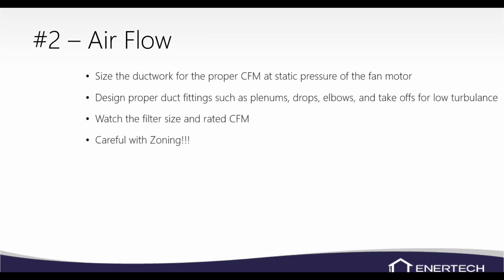Zoning, you can run into a problem with zoning. We do like to make sure that you have a bypass damper on your zoning. So if you have a small zone that's calling, we don't overload the unit and cause it to lock out on low pressure or high pressure because we're not getting enough airflow across that coil. So we can definitely do zoning. Just make sure we're installing a bypass damper, whether that's a barometric or an electronic bypass damper.